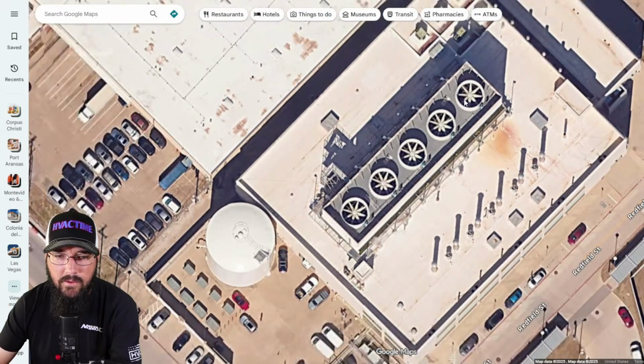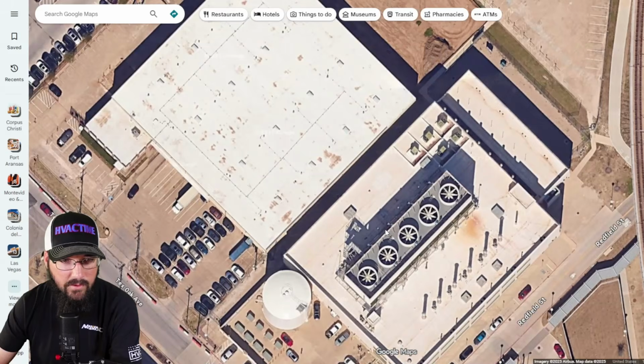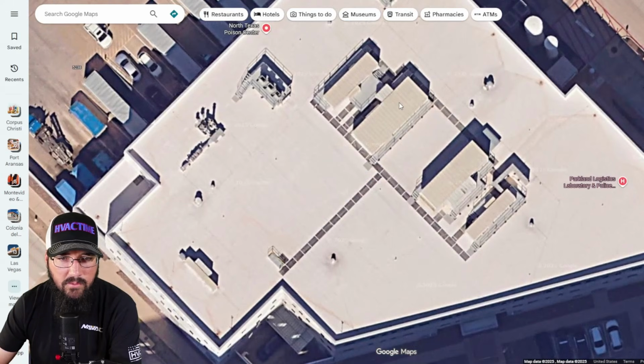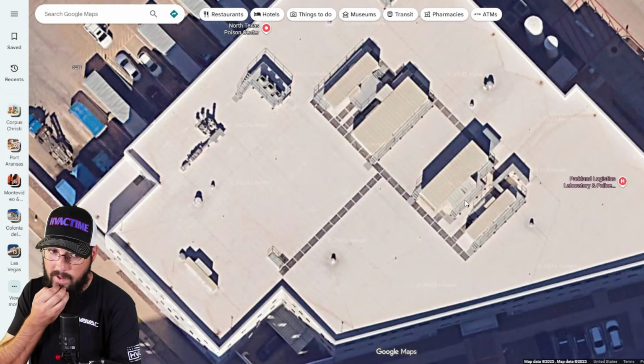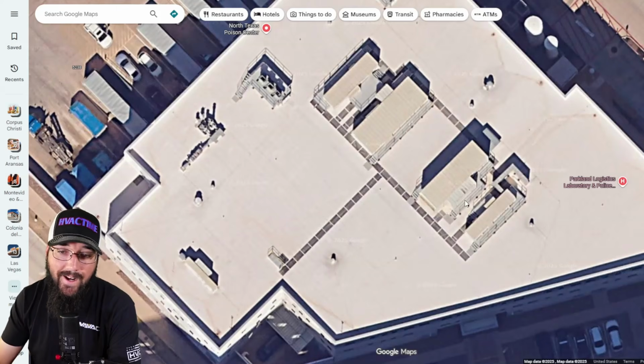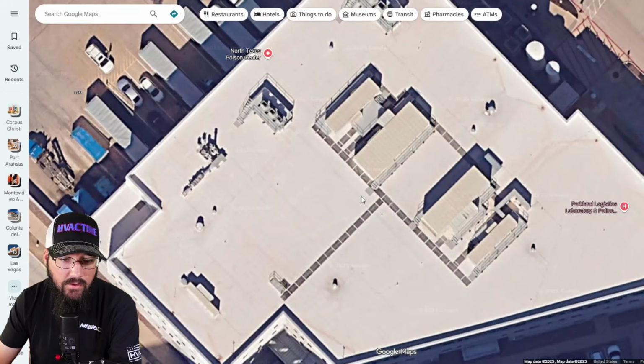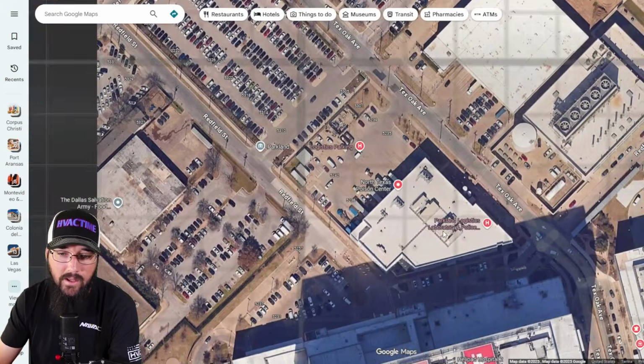Ooh, look at all these towers. Got some rooftop units, here's some. Let me point this out. These are air handlers - the reason I can say that is, where's the condenser fans? Every time we've seen an RTU, we had condenser fans. In this example, you can look at this. There is no condenser fans on this top deck. These are just air handlers. So that's one way you can quickly identify which is which.